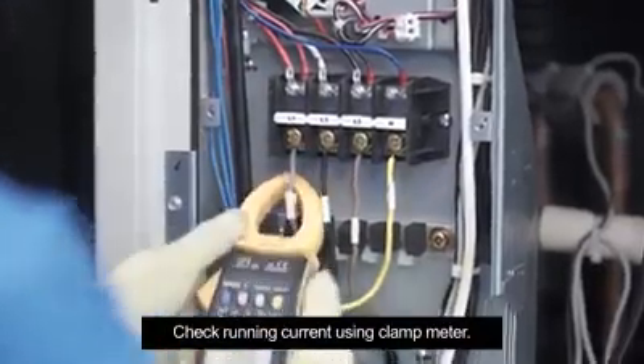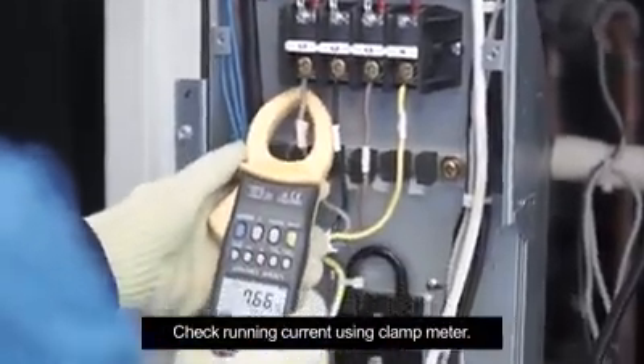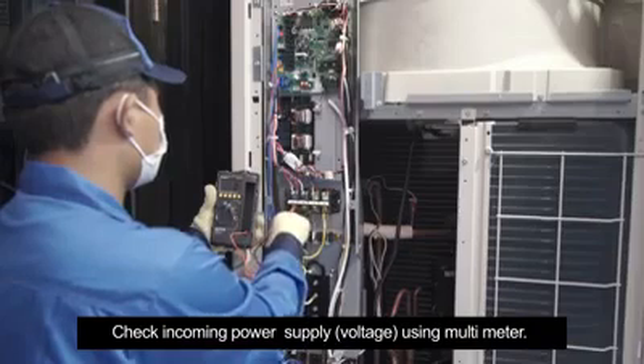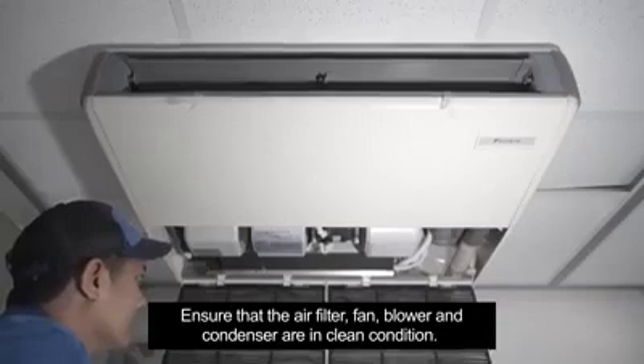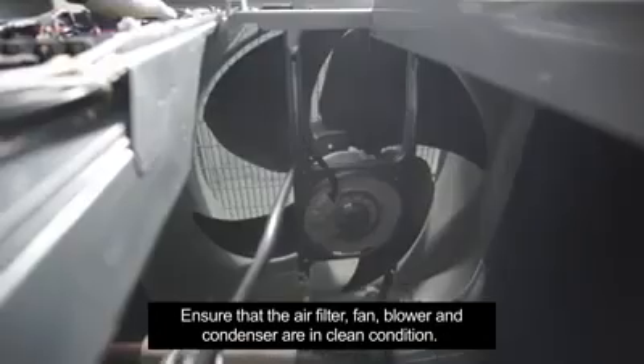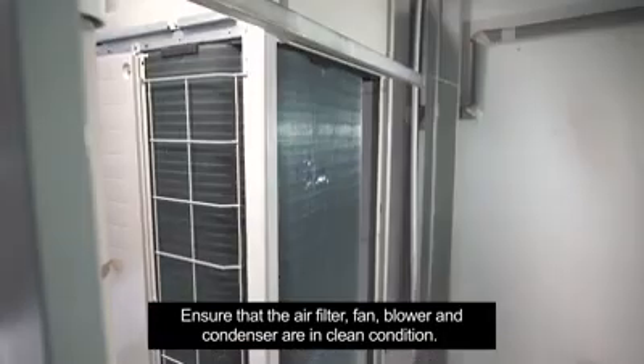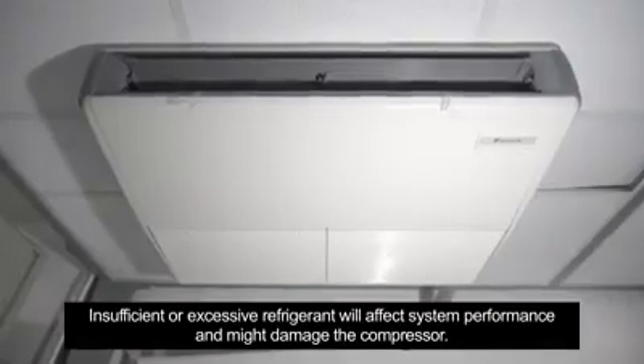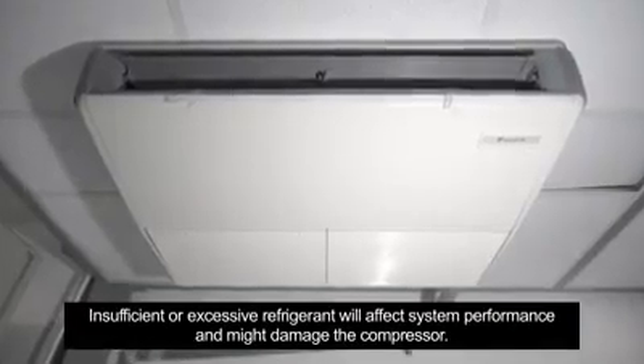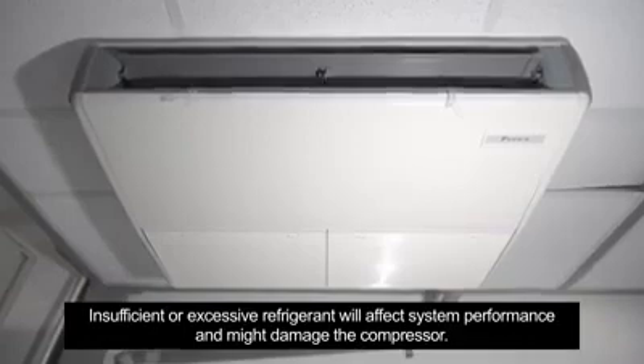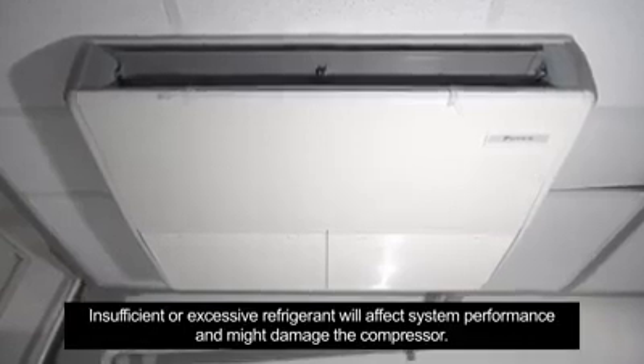Check running current using clamp meter. Check incoming power supply, voltage using multimeter. Ensure that the air filter, fan, blower and condenser are in clean condition. Insufficient or excessive refrigerant will affect system performance and might damage the compressor.